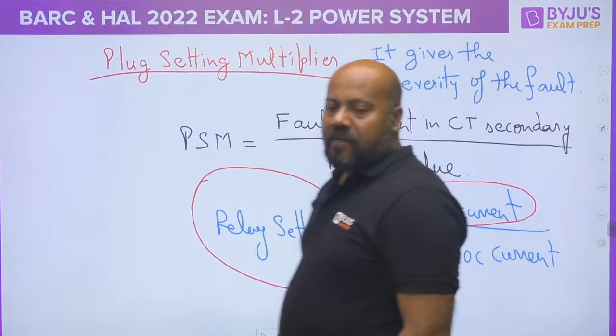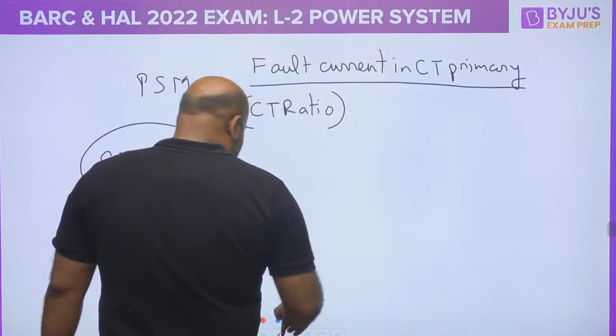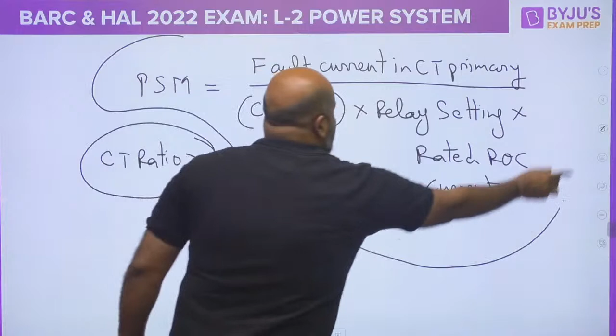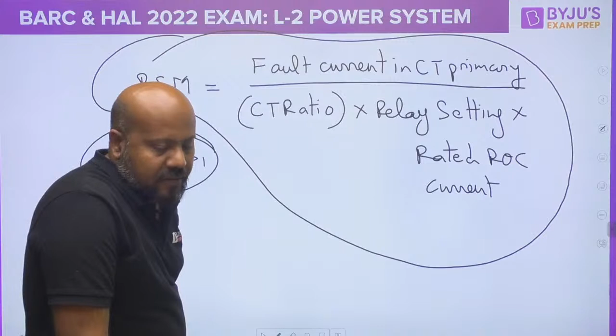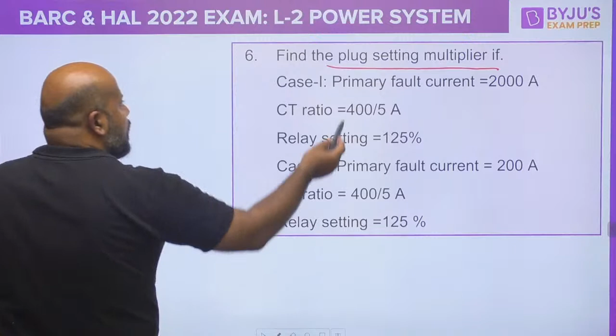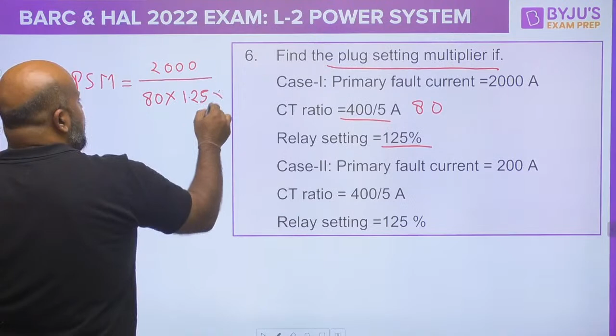What you are doing is changing the number of turns of the relay operating coil. So you will be getting it as pickup current divided by rated RoC current. The rated RoC current is fixed, but the pickup current is going to be decided by the relay setting. What is relay setting? Just change the number of turns of the relay operating coil and you will be able to have different values of the pickup value for the relay. So in terms of the pickup value, you can write relay setting multiplied by the rated RoC current. So this formula now goes as relay setting multiplied by rated RoC current. So this is going to be your final expression for the plug setting multiplier.